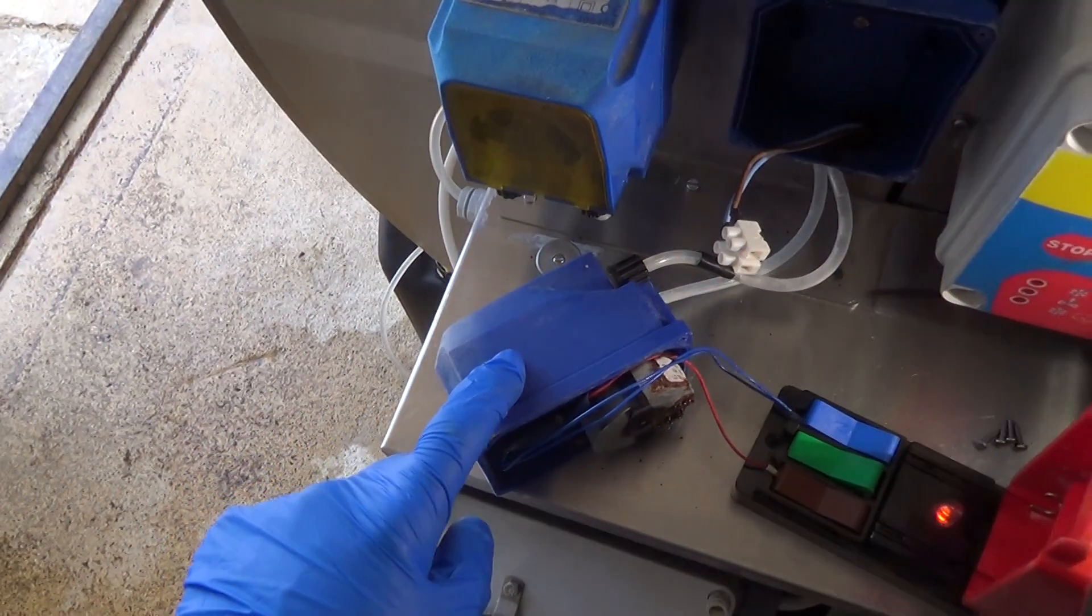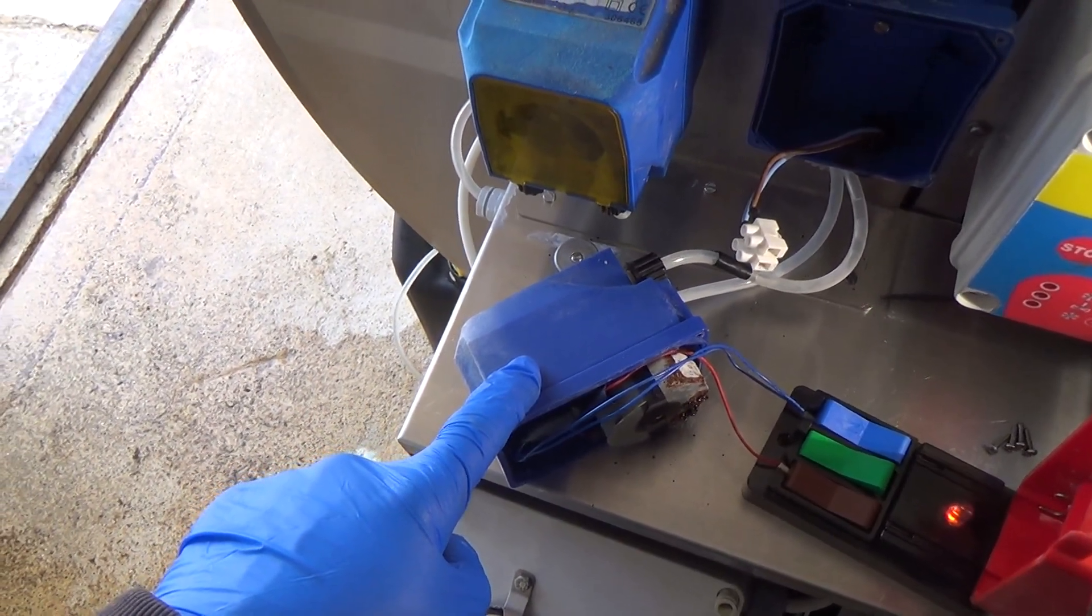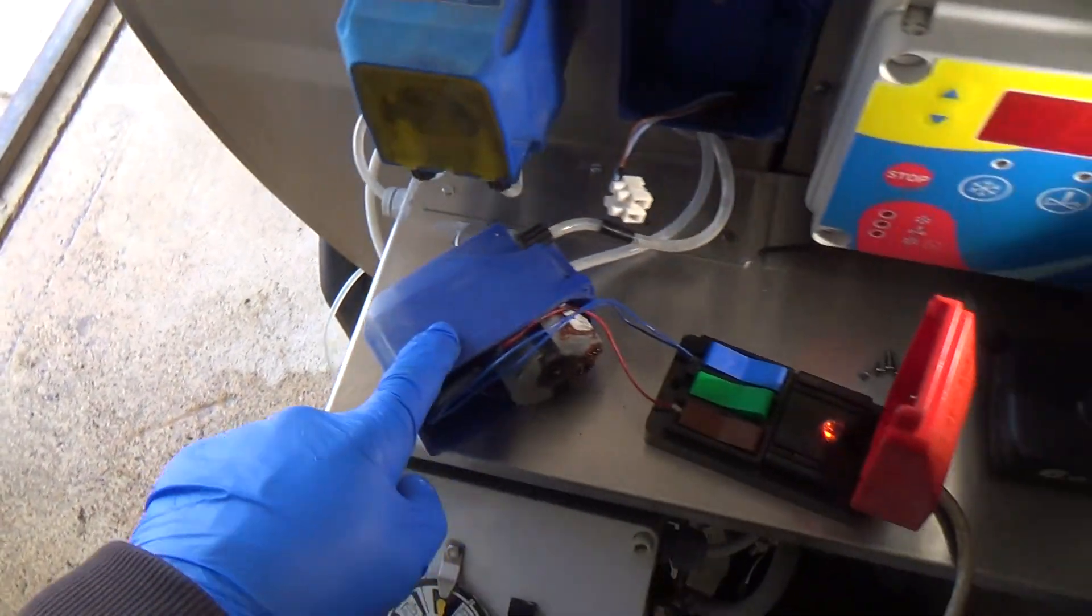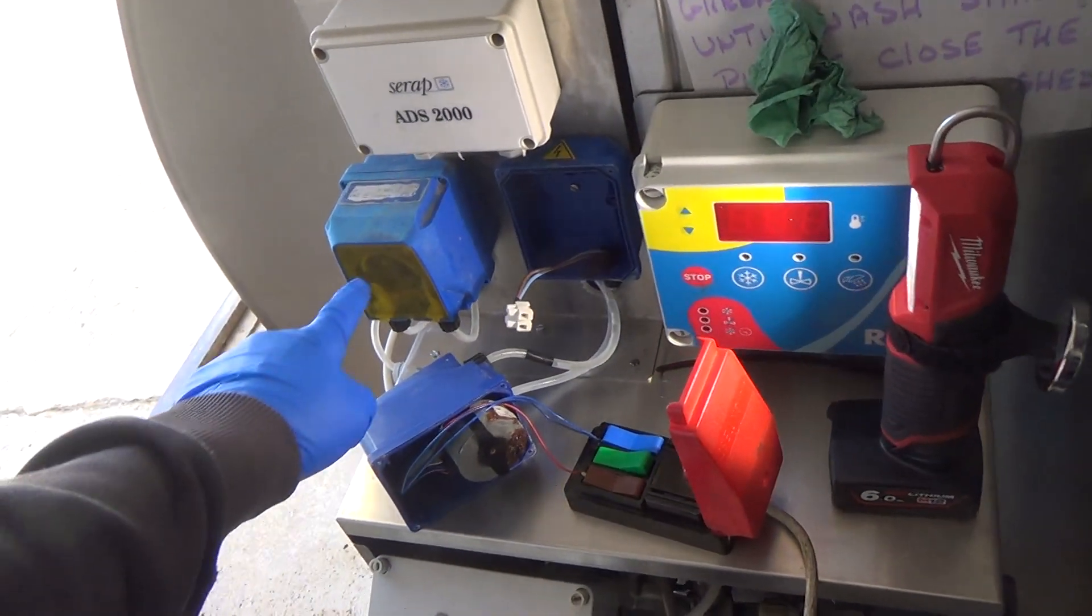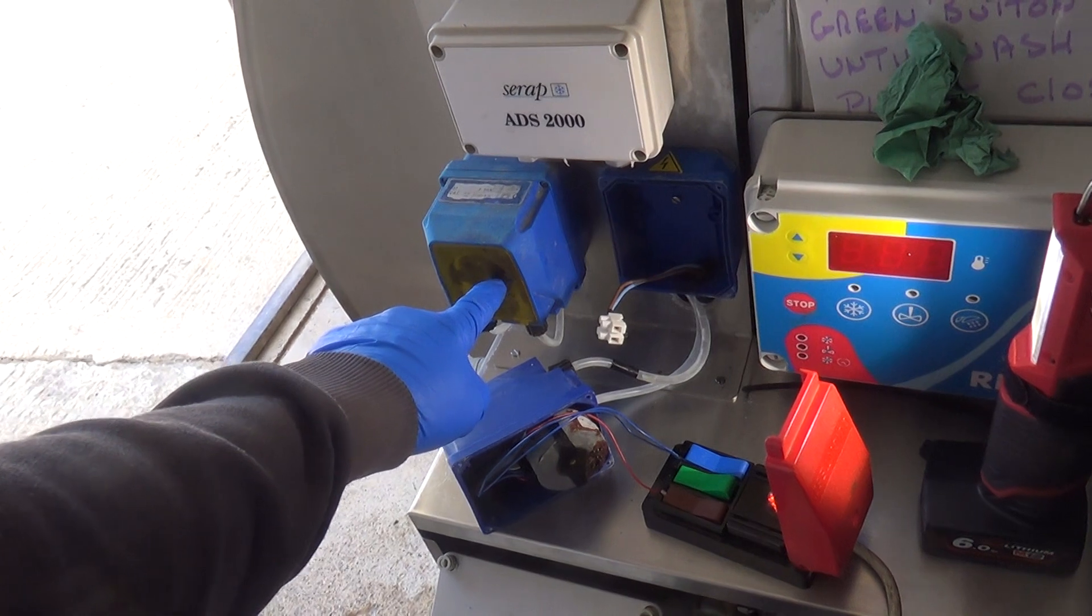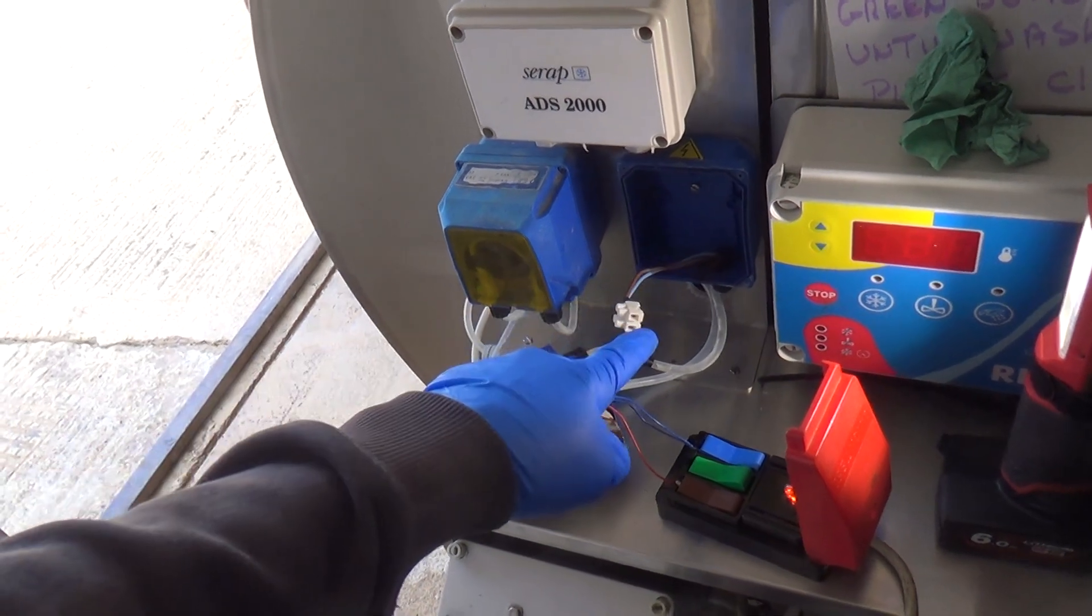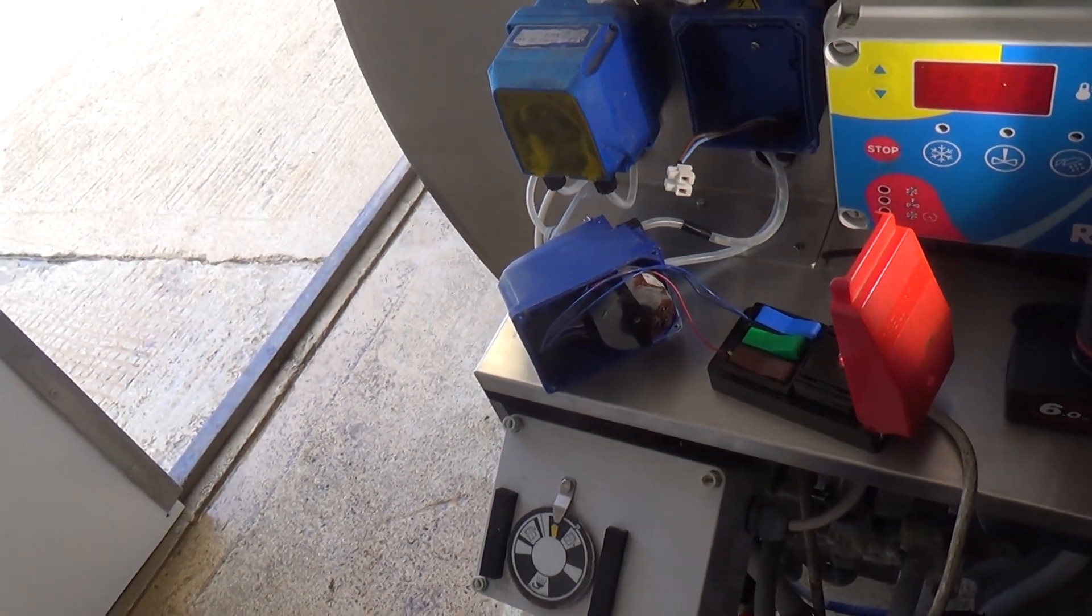This one, where it does the hypochlorite final rinse or rinse before, I think it's the final rinse, is a mains pump. So you need to be very careful that they look the same, but you need to check that you're not putting a 24 volt pump on a 240 volt feed, because it will blow up. And I have seen that done.